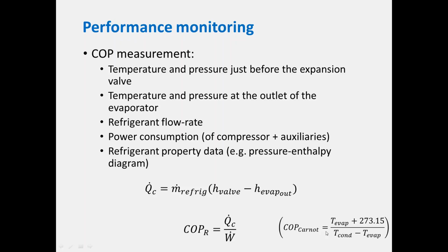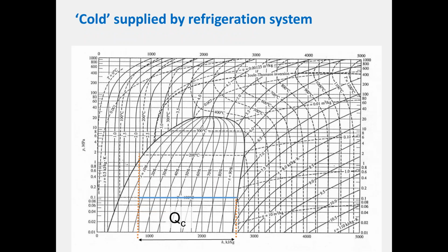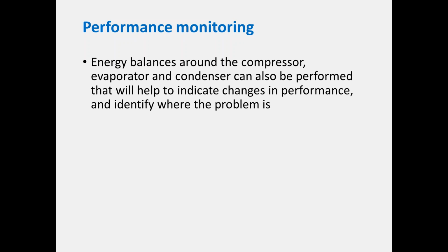That just gives you the upper limit, but rather than worrying about how close to that you are, if you monitor your COP, it'll give you a preliminary diagnostic tool to identify that something is wrong. If you want to work out where it's wrong, you really need to do some more monitoring. Preferably you'll do energy balances around those four units, and that will allow you to locate, hopefully, where the problem is, so you can rectify it more quickly.